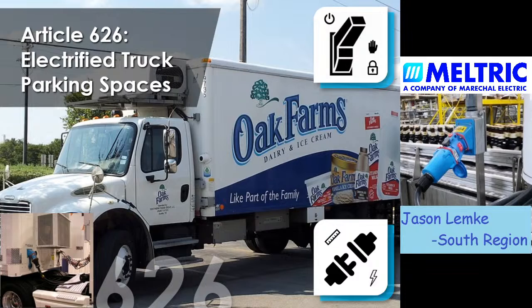Now, from my experience of reading through the National Electrical Code, you don't have to use a horsepower rated plug-in receptacle. There are abilities to do non-horsepower rated plugs and receptacles, but you still have to meet the amperage requirements for locked rotor condition, because there is the opportunity for that plug-in receptacle to have more current through it than what the plug-in receptacle is rated for. So you want to make sure that you can handle those fault conditions. So the 2 ways that we do that in motors is making sure that you have a horsepower rated device, and then for your short circuit make and withstand while the overcurrent protective device is tripping, you want to make sure that you're coordinated with your available fault current through the device.